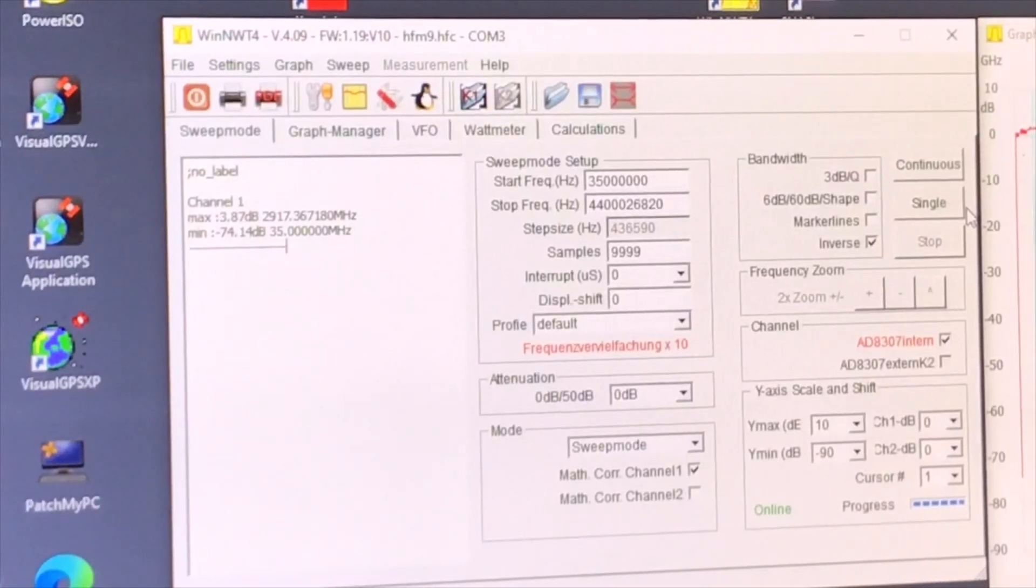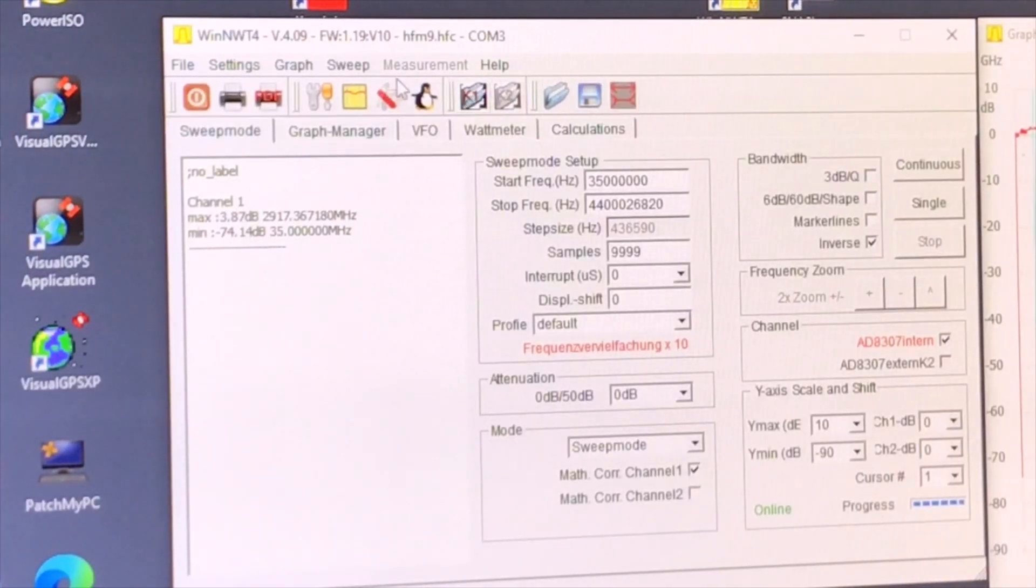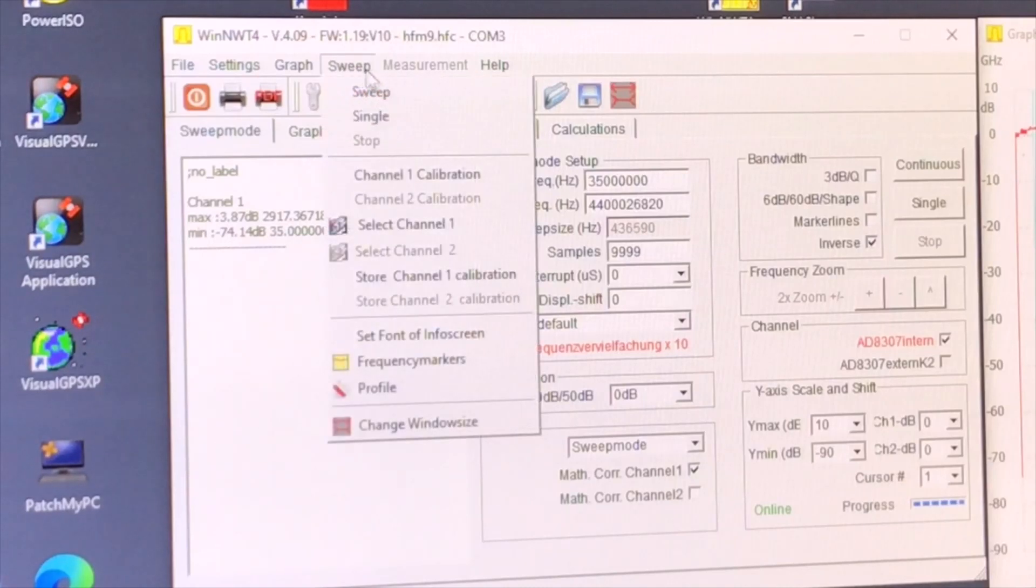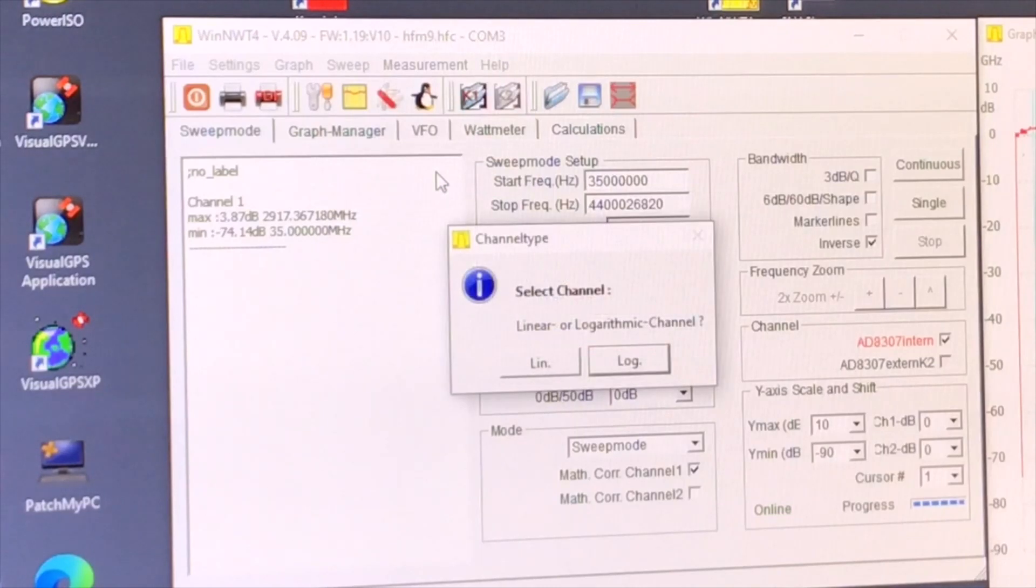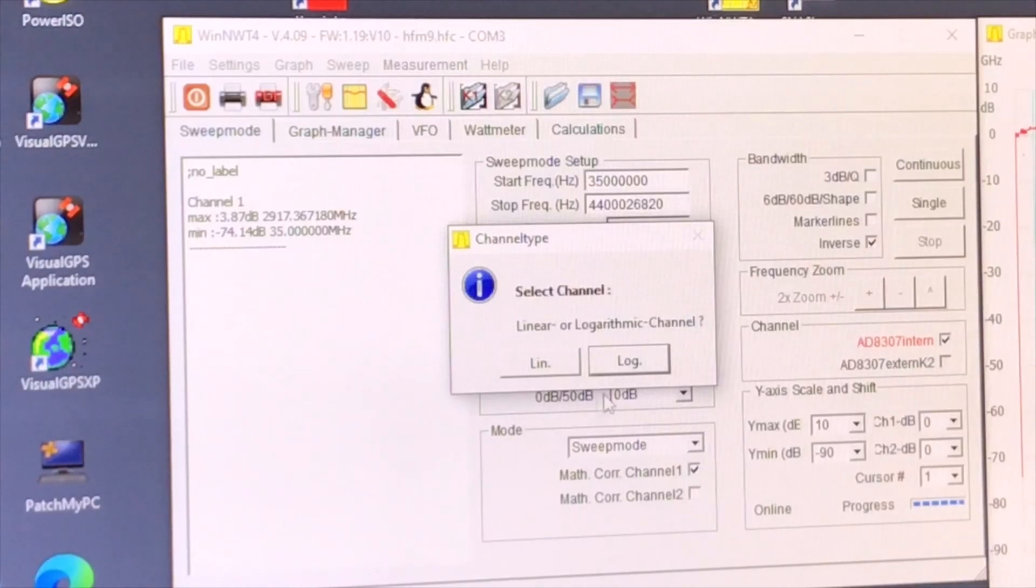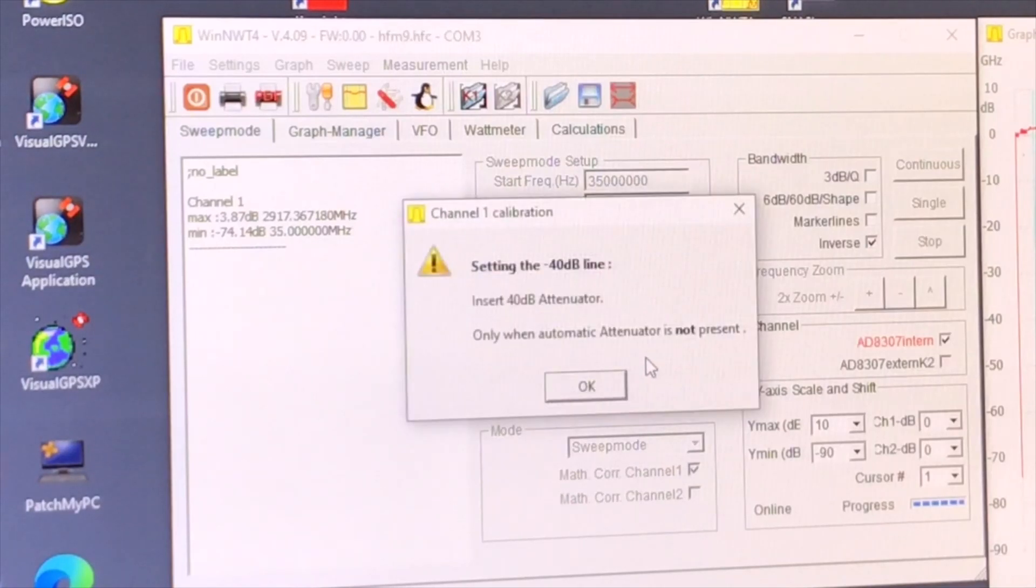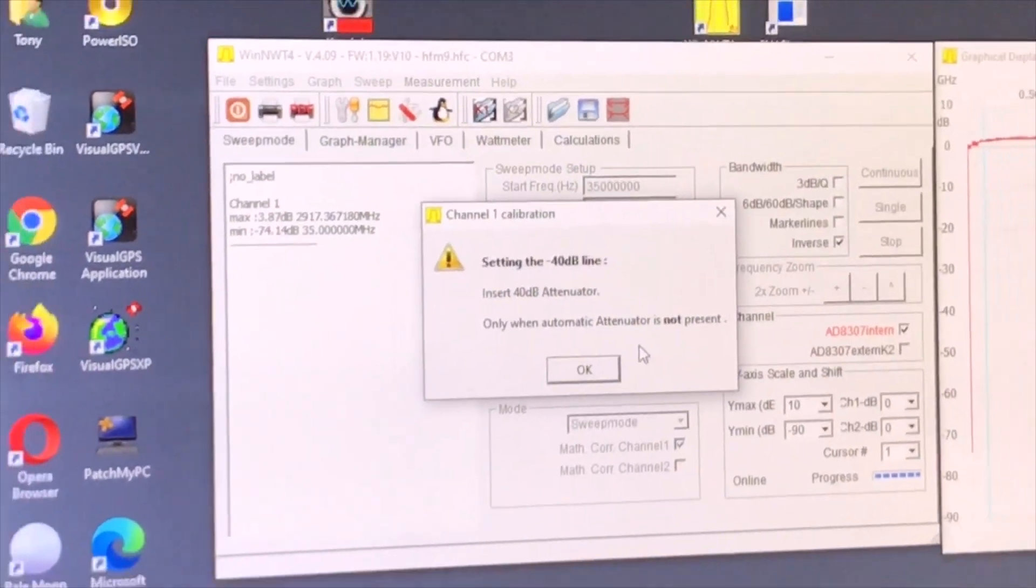So it was a fair question of Otavio. How can I get this better? I'm zoomed in now. What you can do here is go to SWEEP channel 1 calibration. And then it says linear or logarithmic. We pick logarithmic, I think, because we have the logarithmic scale here. And then it said, okay, put your 40 dB attenuator. So we're going to do that.